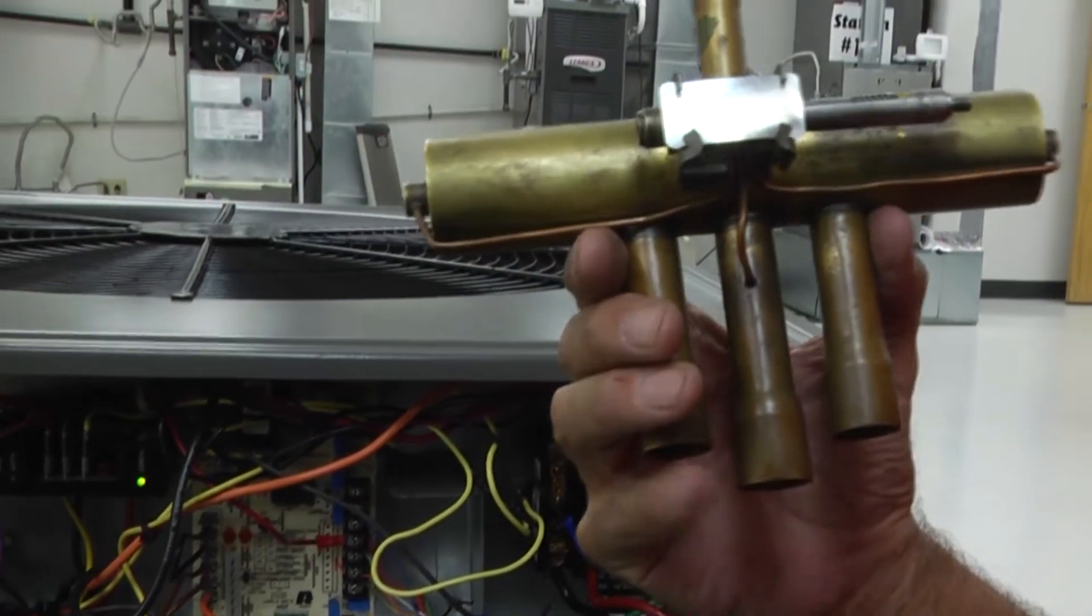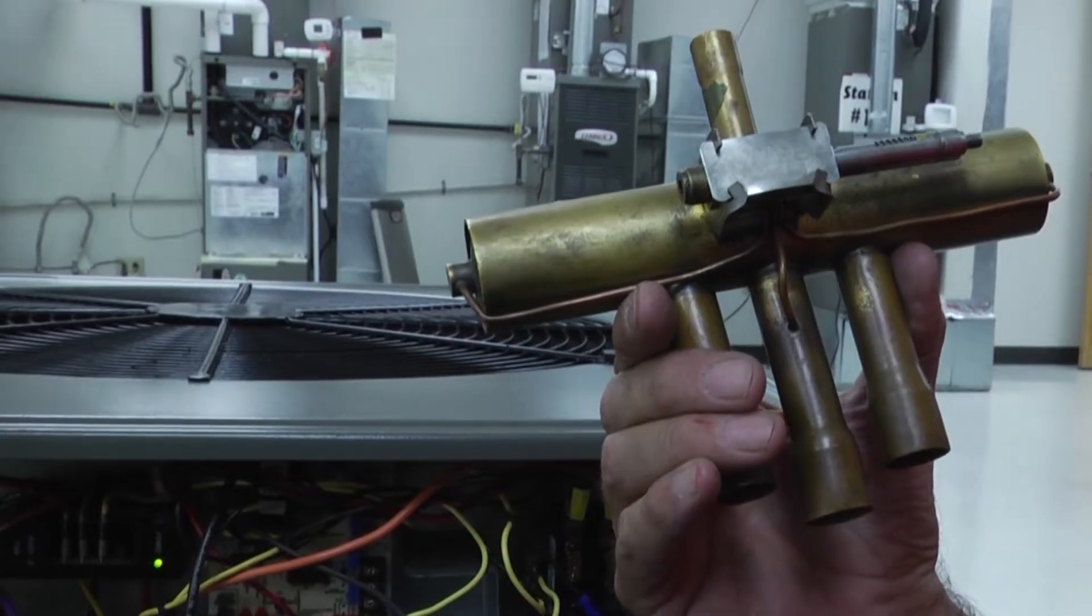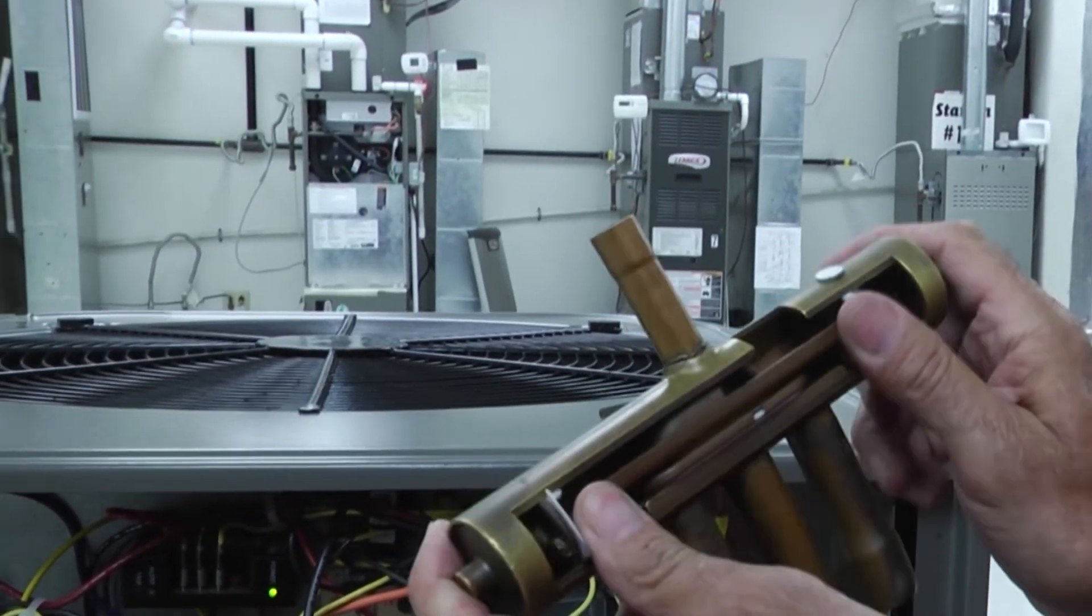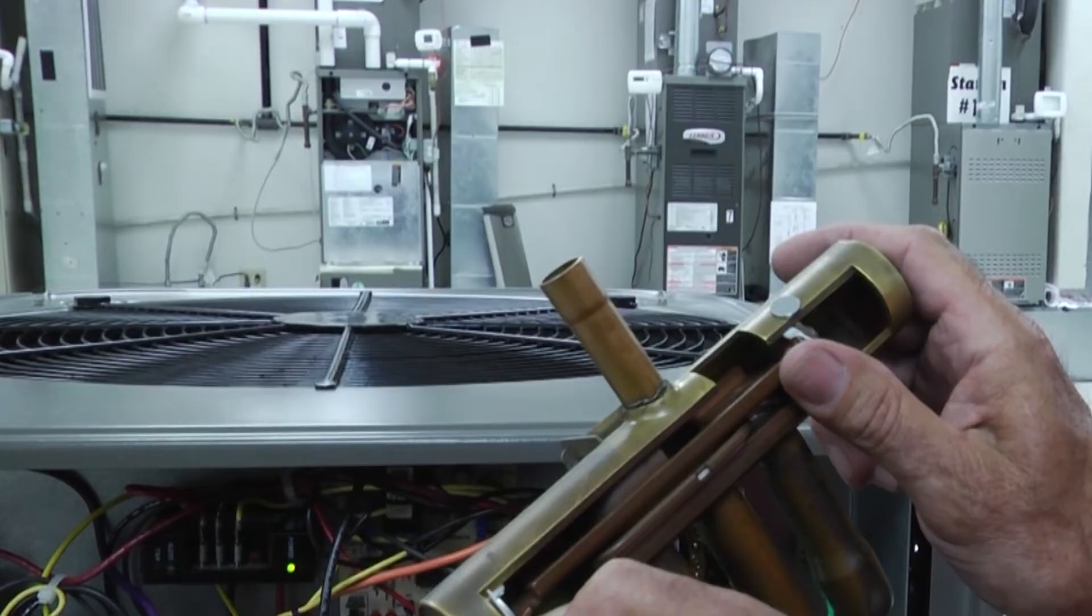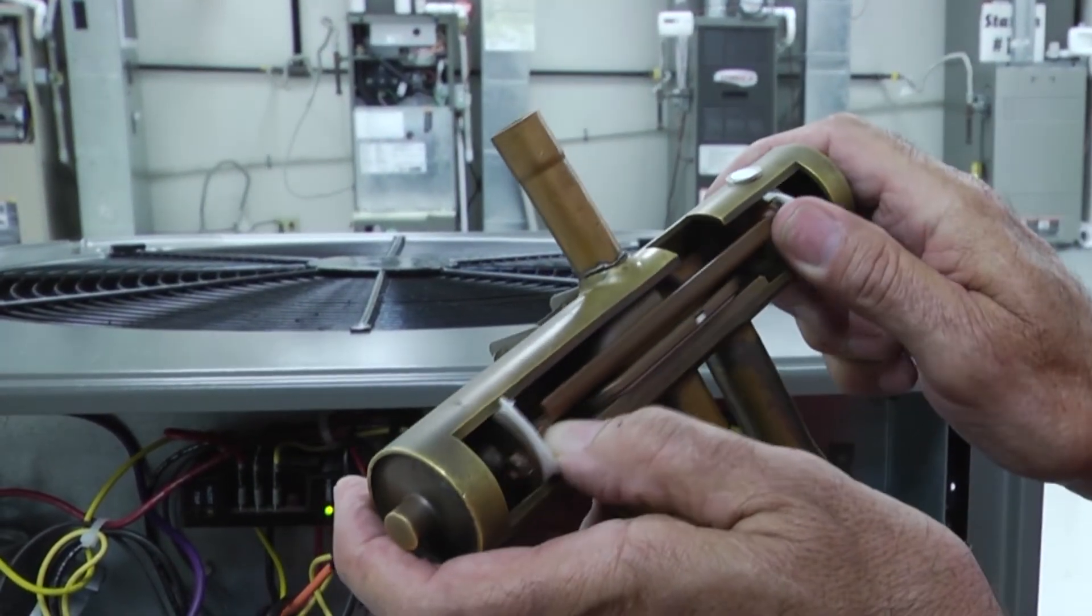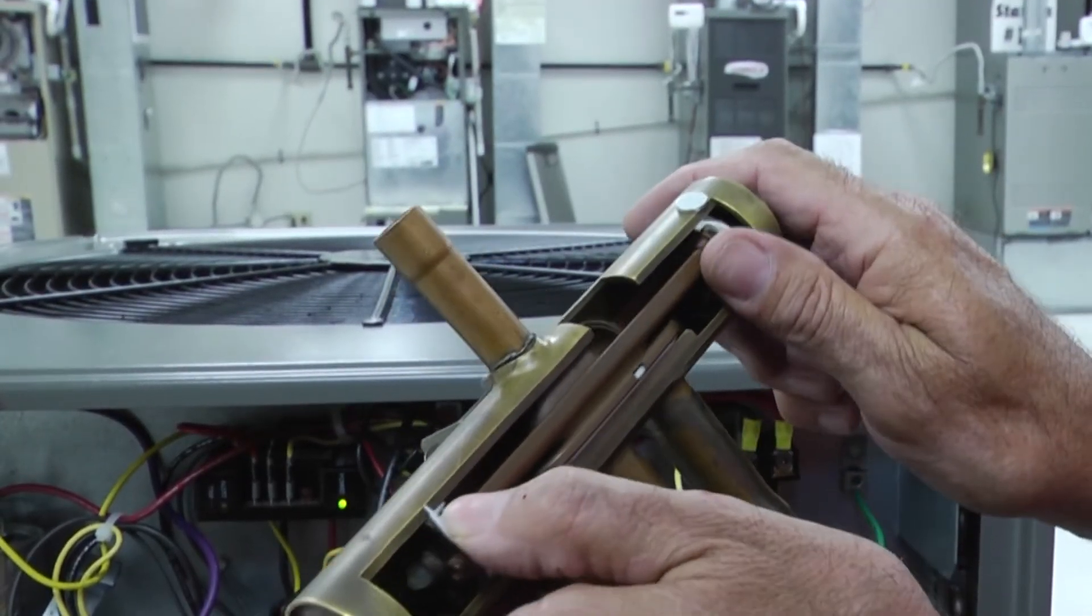I thought what we would do is quickly show a couple ways to diagnose problems or verify a reversing valve is working correctly. We have a cutout of the valve to show what it looks like on the inside. I've also put a little magnet here that you can watch shift back and forth.